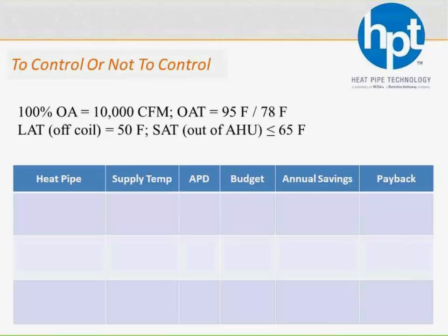So I want to look at a quick example of why and when to use control valves. Here's an example: 100% outside air, 10,000 CFM. Let's use those standard operating conditions, 95, 78. Let's say it's a 50-degree dew point coming off the cooling coil, and let's say that the warmest air you want delivered out to the space is 65 degrees. You don't want it to get any warmer than that.